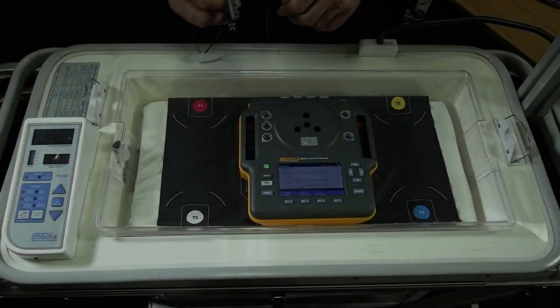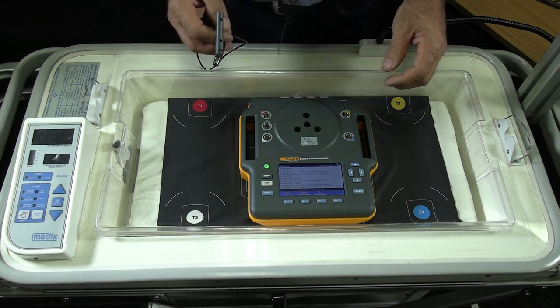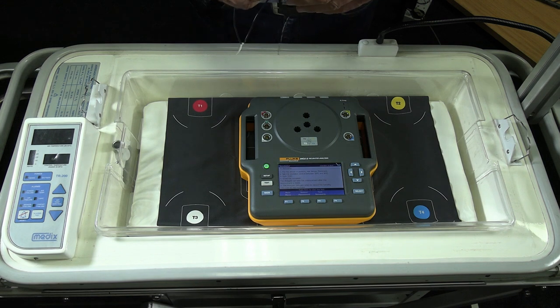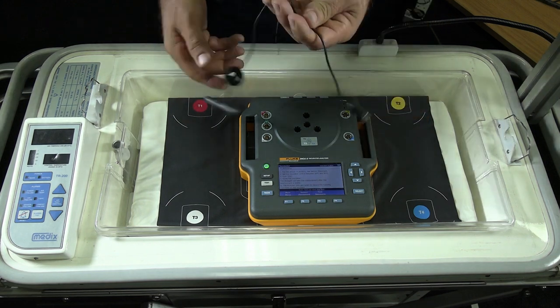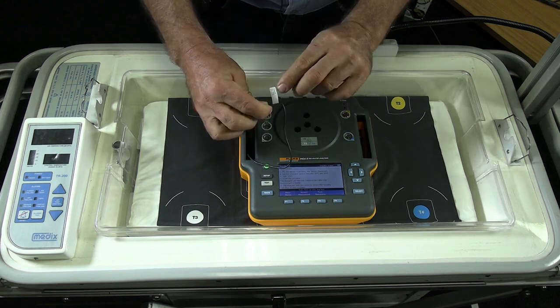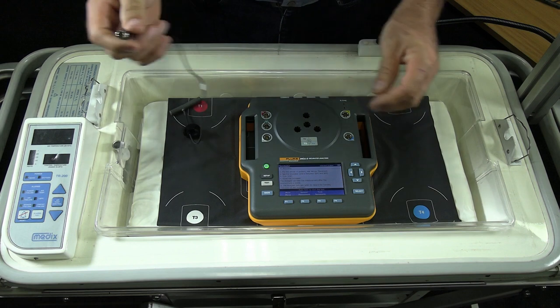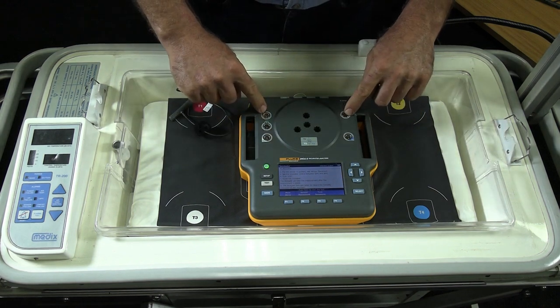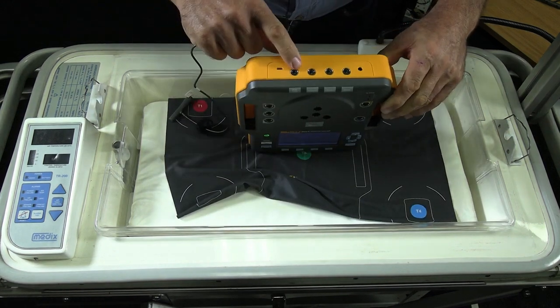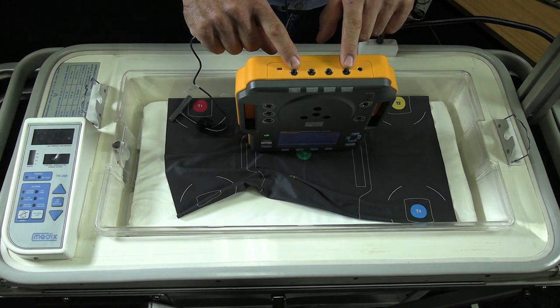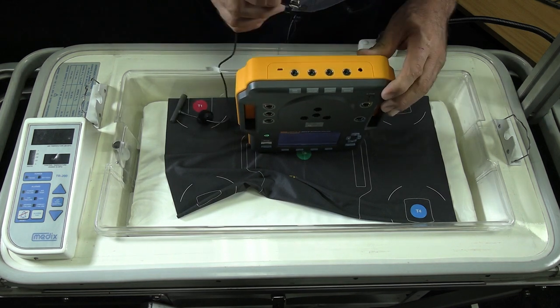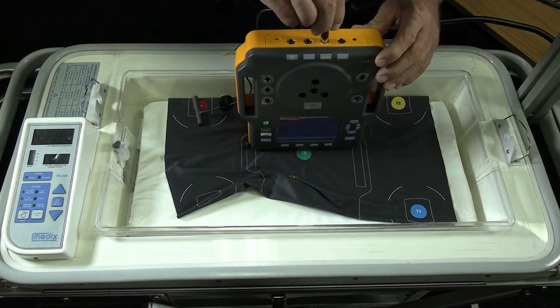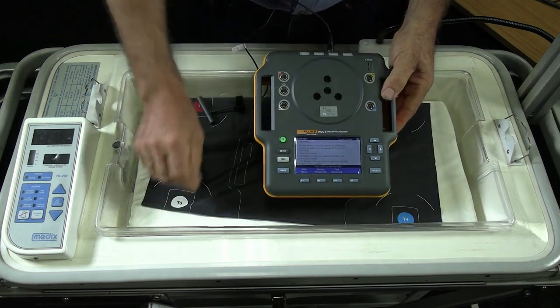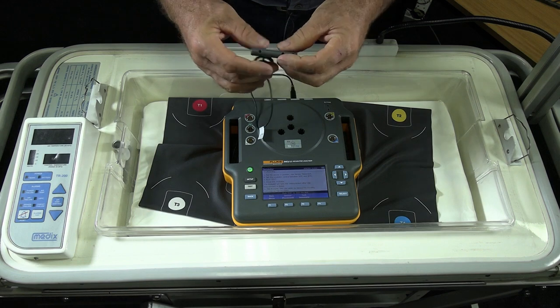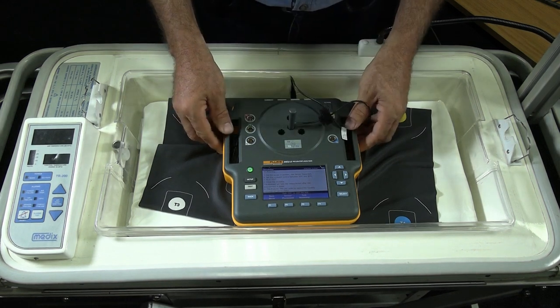The next feature we want to test on this unit is when we want to do humidity testing on an incubator to make sure that the humidity inside is not too high or too low for the baby. We make use of a humidity sensor. Again, you will see that on the label, it will tell you that it's a humidity sensor. And other than the temperature sensors, which all plug in on top here, the skin temperature, the airflow, the humidity, and the sound probes plug in on the side of the unit where your power connector is. So humidity, we just plug the unit in there. And then for the test, we place our unit back in the center of the mattress, and the position for the humidity sensor would then be the center position, center of the mattress.